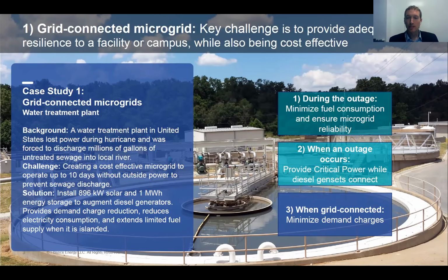So what they did was add solar PV, diesel, and a battery. The battery complements the PV nicely, helping with the intermittency of solar generation and shifting some of that generation to the evening so you use less fuel, because getting to 10 days would require a lot of on-site fuel. If you have a requirement like that, you need to be as efficient as possible with the fuel you do have.